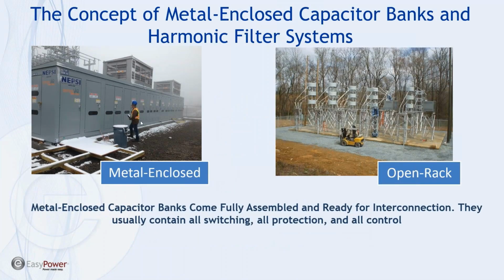So just briefly, the picture on the left shows a metal enclosed harmonic filter system. This system comes with all switching, all protection, all control. This is a C high pass filter system consisting of 2 stages. It's located at a wind farm in northern Quebec. It was roughly rated 16 megavars, and it had SF6 switches in there for switching the stages. It had iron core reactors for tuning the capacitors to the 4.7th harmonic. That incoming air disconnect switch, ground switch. The stainless steel boxes you see on top are resistors. So it's a packaged solution. And this is essentially what NEPSI builds at our factory in Queensbury, New York.